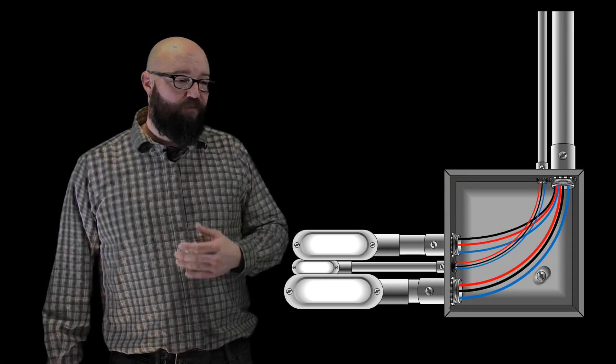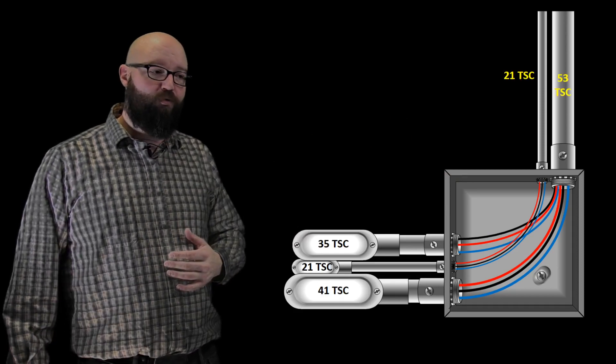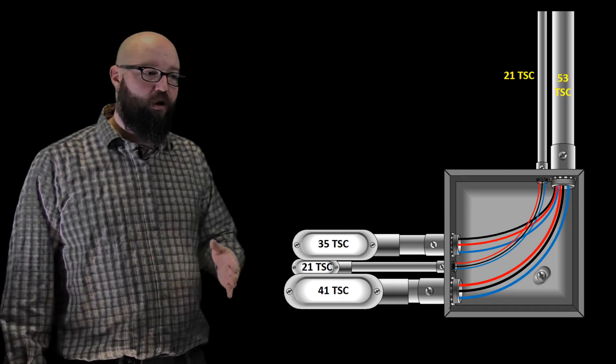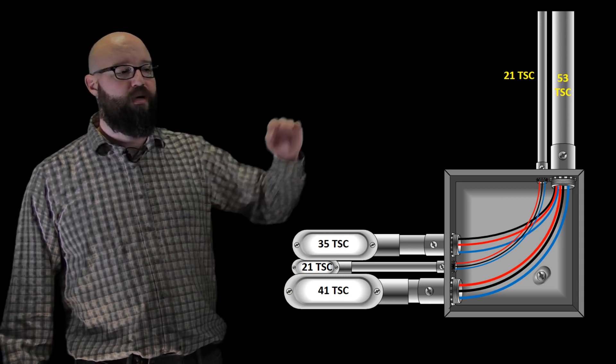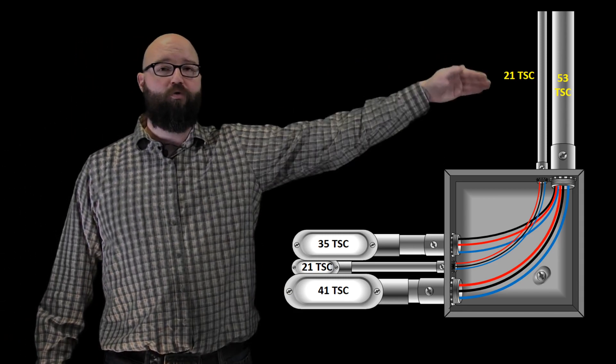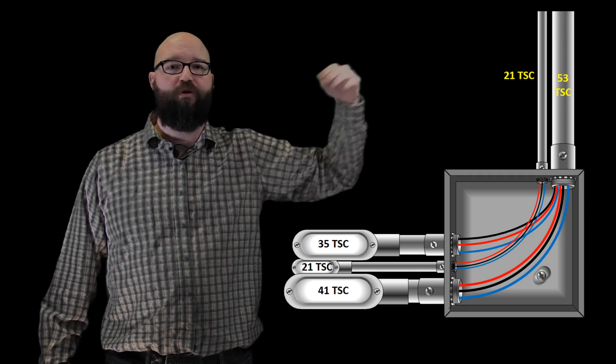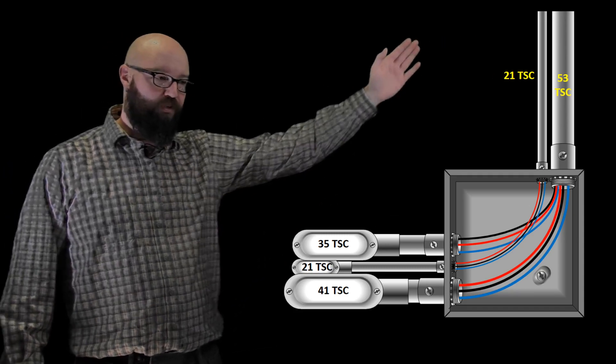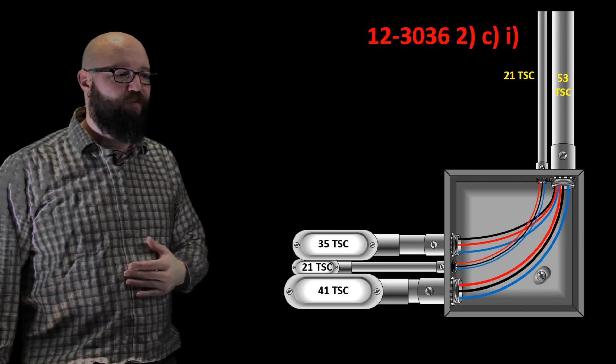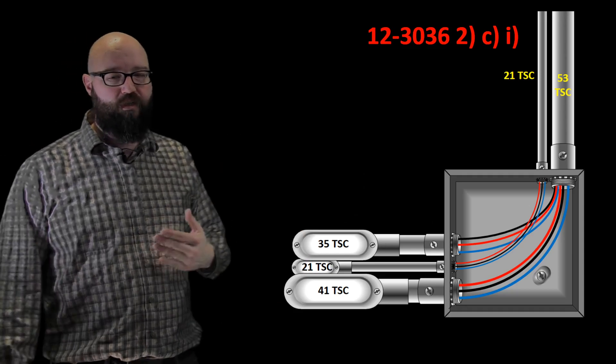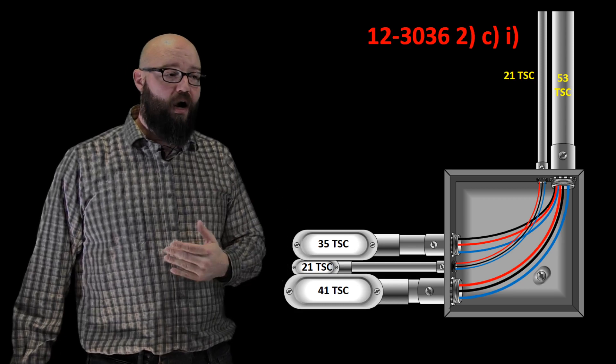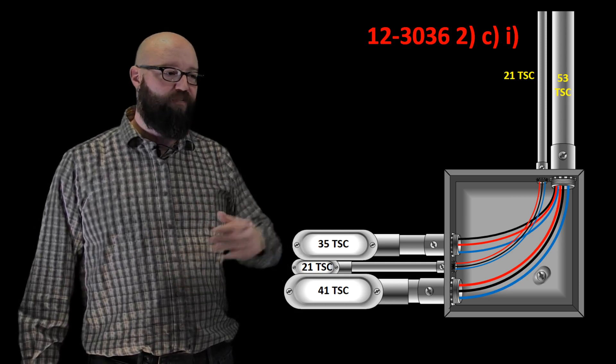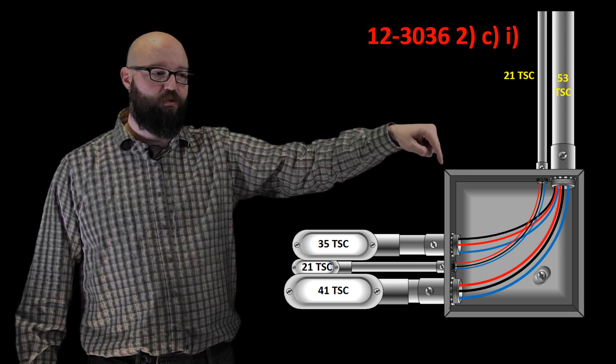So the first dimension that we're gonna focus on, if we look at 12-3036, we have all of our conduits here listed. We have our 41, 21, 35 trade size conduit, and then on this adjacent wall we have our 21 trade size conduit and our 53 trade size conduit is the furthest there. So we're gonna focus on 12-3036 Sub Rule 2 Item C Item I first, which tells me what I want to do essentially is if I look at this wall right here, we're gonna look at this wall first.